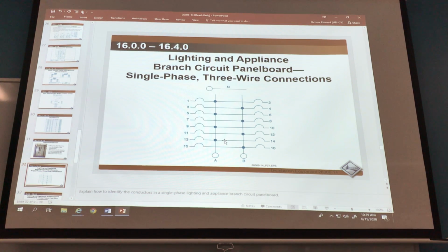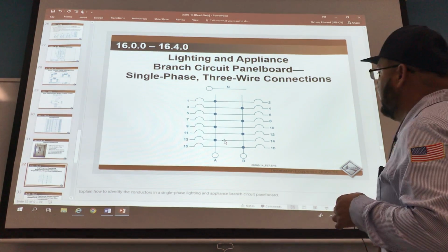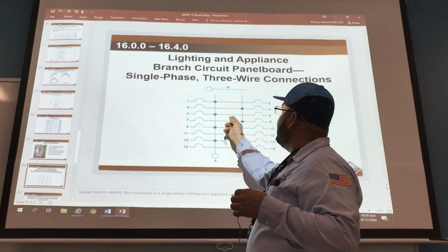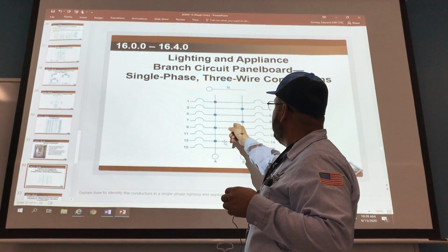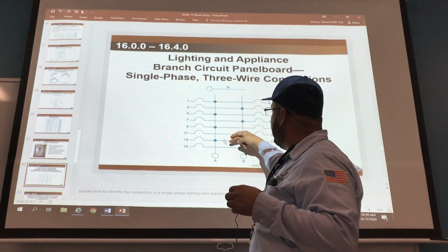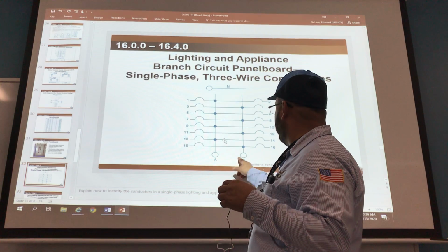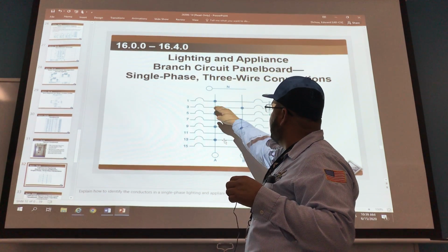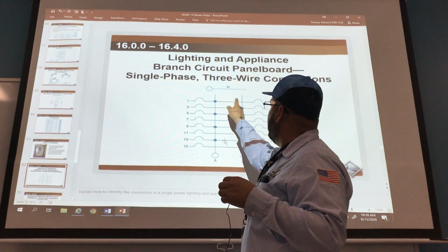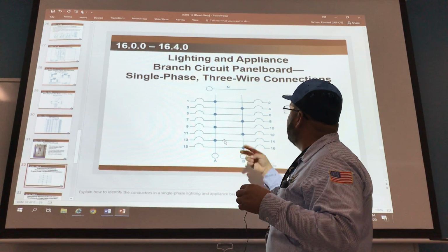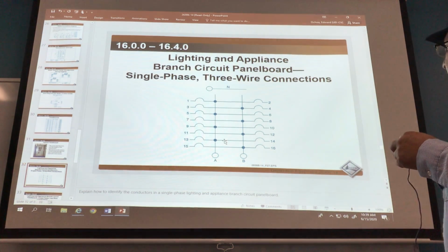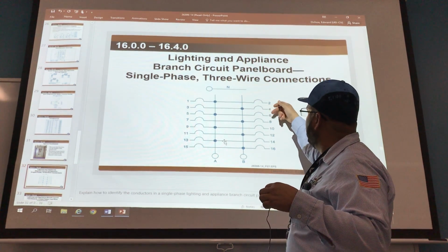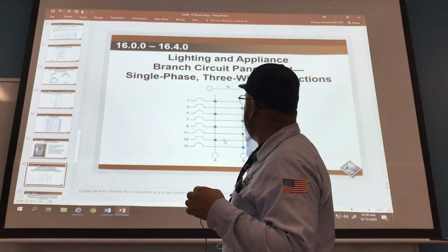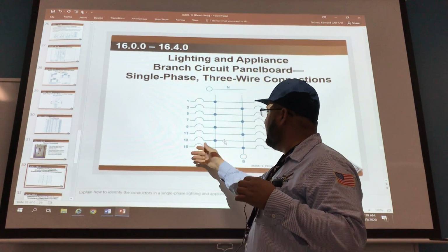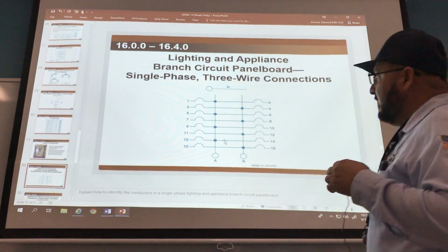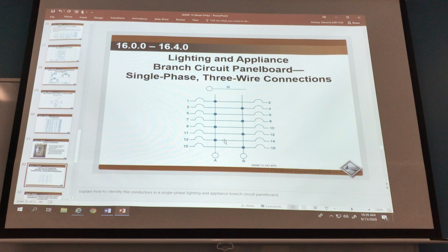This is what it looks like internally - these are your buses, ABC, or if it's single phase, AB, AB, AB. Here it is, yeah, AB - you can see how it's connected, the A's and B's connected, so it's a single phase 3-wire system. These represent breakers, and you always count 1, 2, 3, 4, 1, 3, 5, 7, 9, 11, 13, 15. Every third one will be blue; when you go to high voltage, every third one will be yellow.